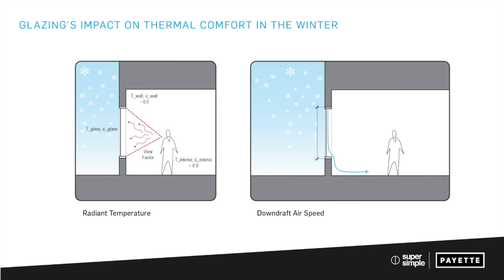There are two main ways that glazing impacts comfort. One is from radiant temperature — because glass has a higher U-value, it's much cooler, and so we lose a lot more heat to that glass than we would to an exterior wall. There's also something called downdraft, where a draft comes off the window. The radiant temperature affects your whole body making you feel cold, whereas the draft is more local — your ankles or your hands feel cold.